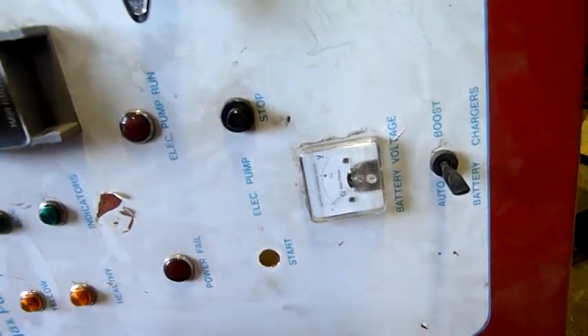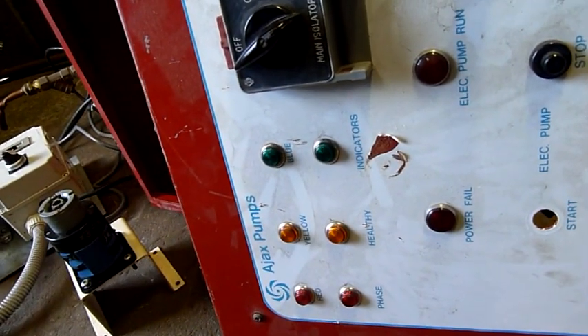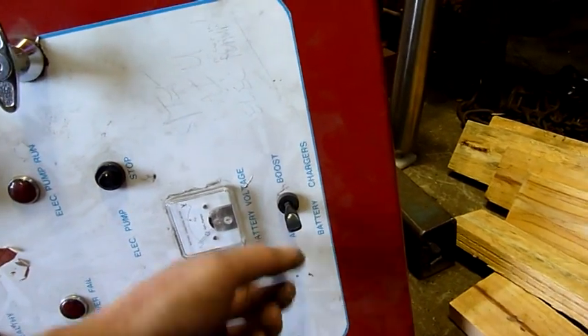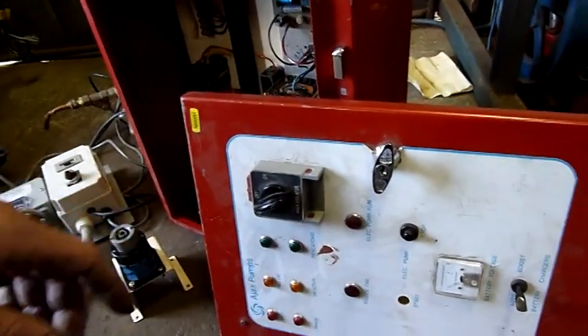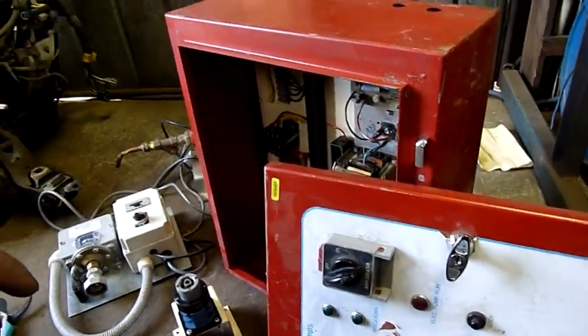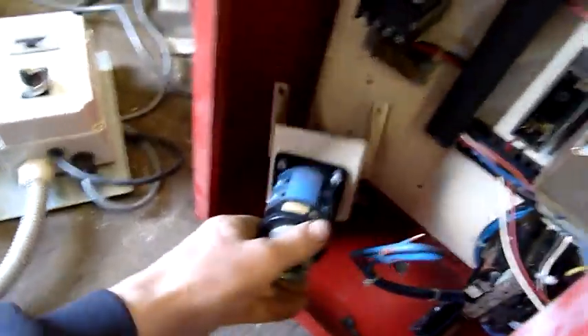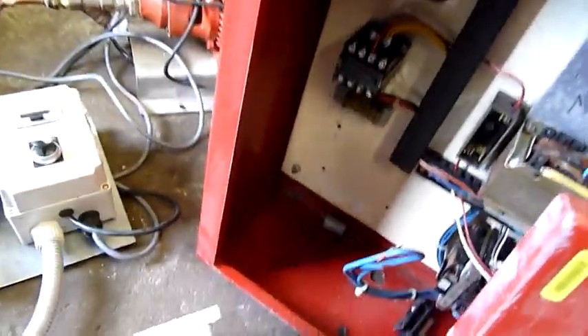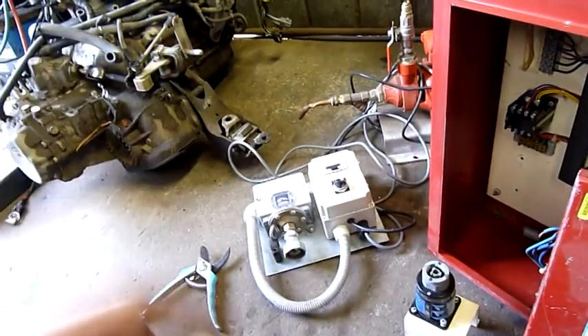It's got a battery condition meter and various indicators. So even if the power goes down, the fire system can still function. There would have been another part of this system that probably looked like a UPS as its backup. Unless the batteries are installed in here — but no, that's where the main switch went, so there's no room for batteries in here. There would have been a separate cabinet.